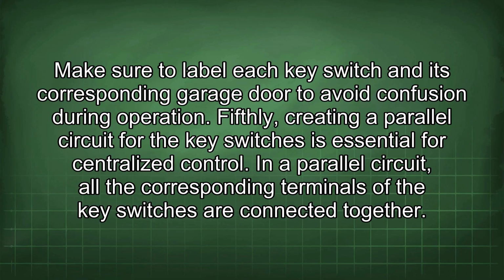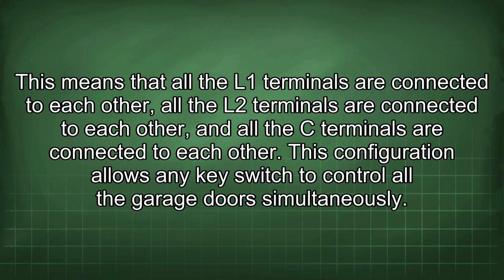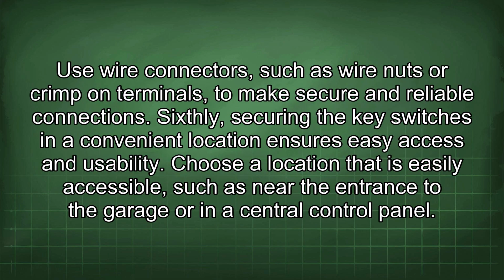Fifthly, creating a parallel circuit for the key switches is essential for centralized control. In a parallel circuit, all the corresponding terminals of the key switches are connected together. This means that all the L1 terminals are connected to each other, all the L2 terminals are connected to each other, and all the C terminals are connected to each other. This configuration allows any key switch to control all the garage doors simultaneously. Use wire connectors, such as wire nuts or crimp-on terminals, to make secure and reliable connections.